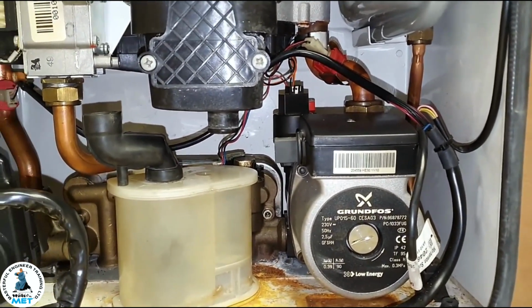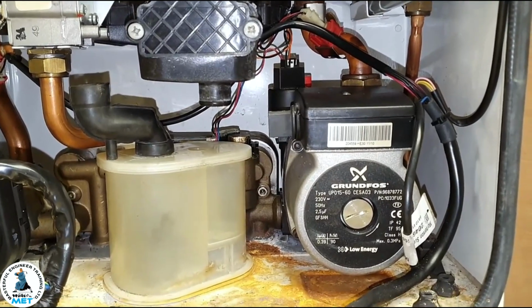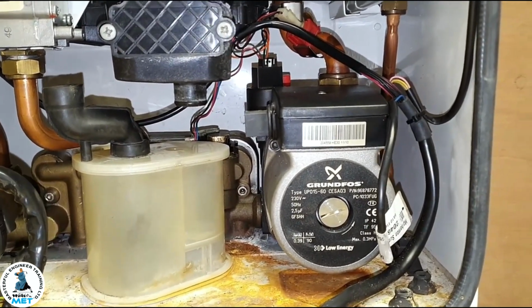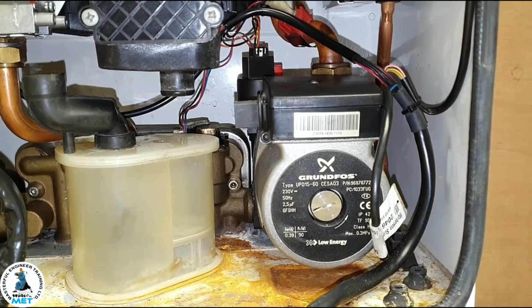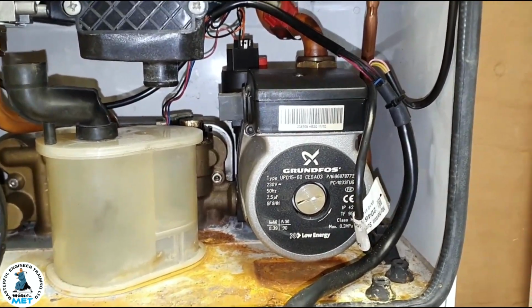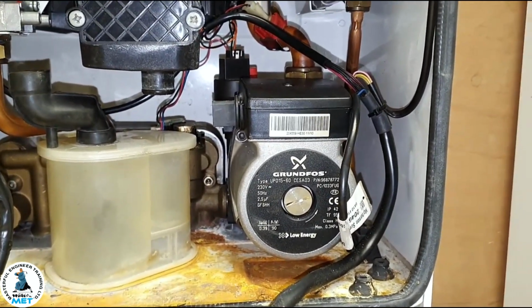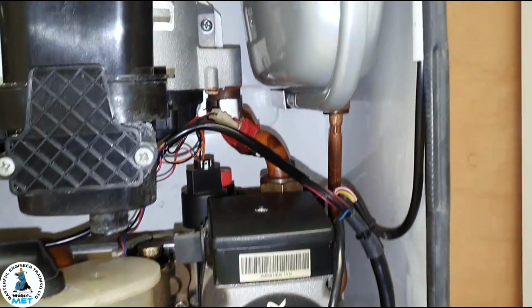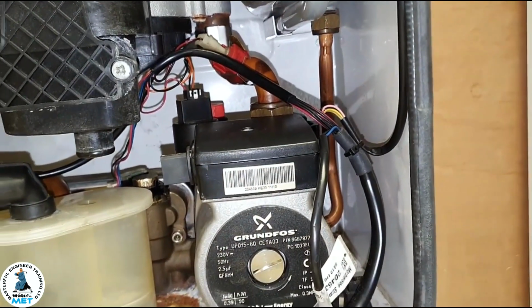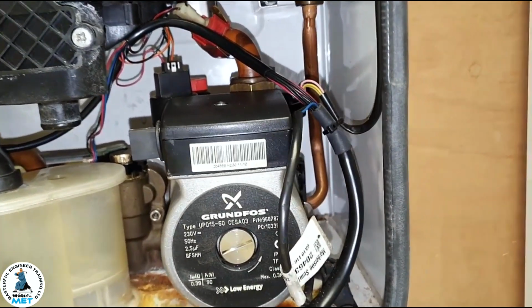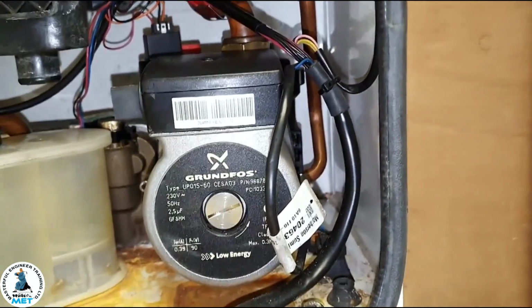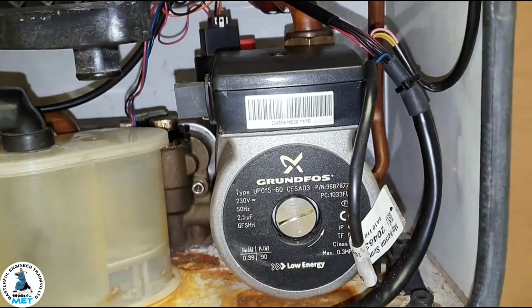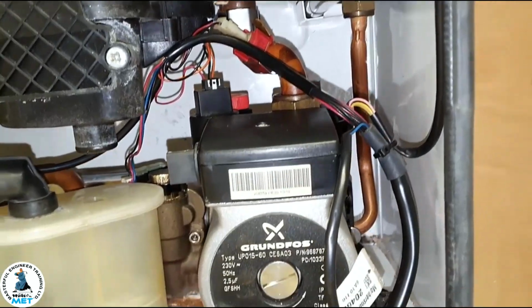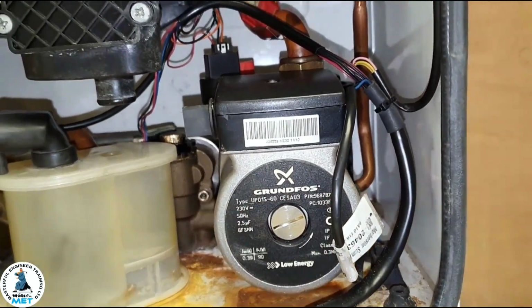So what would you use, Tony, to clear any blockage in that pipe? As I said, you'd have to physically take it out, and once you can see it, you can just get a little screwdriver and clean it out. Or the pipe itself could be blocked just there, but you can see how difficult it is to get to. You haven't got much room, it's very tight, and that's one of the things I don't like about these particular boilers.